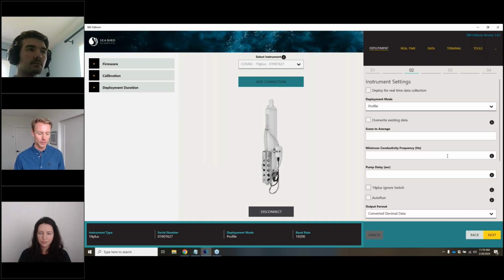On this panel, panel 2, is all the settings that apply to this specific instrument. What shows up here is dynamic. So if you're connected to a 37, you're only going to see settings that are applied to that instrument. It also does a lot of checking to make sure that you're putting in valid settings. So if I put in, say, scans to average is 0, that's not valid. It has to be an integer between 1 and 240. I'll start with 5 because that will be a nice round number.